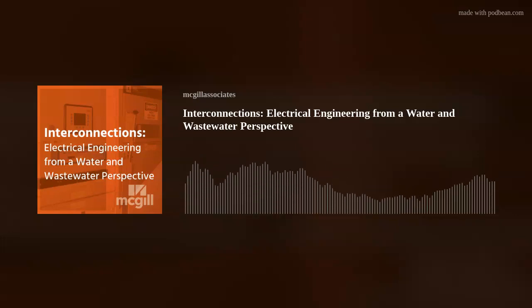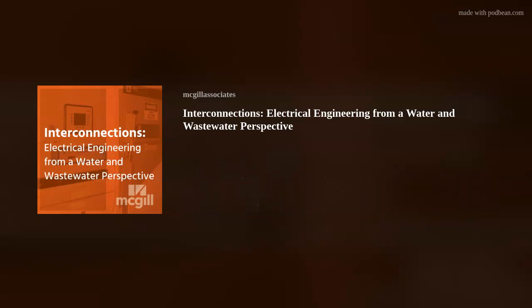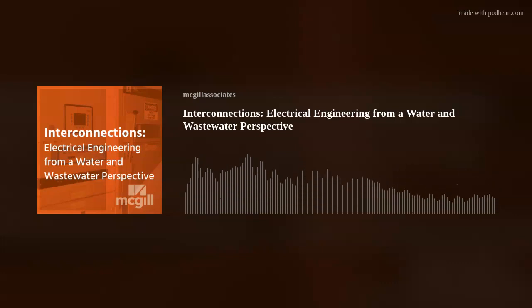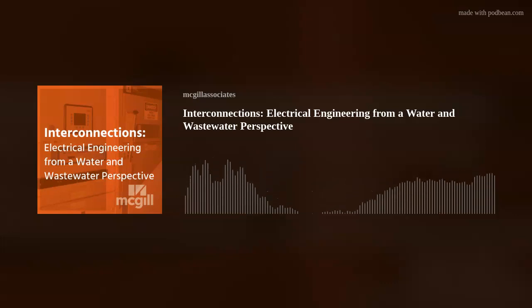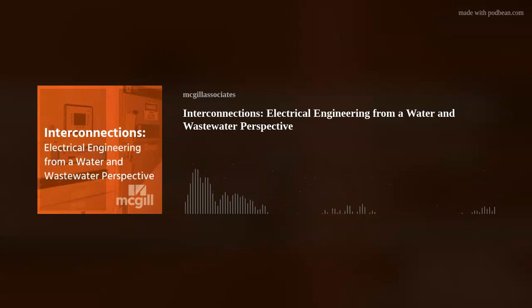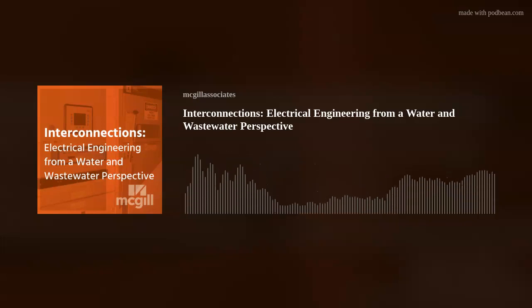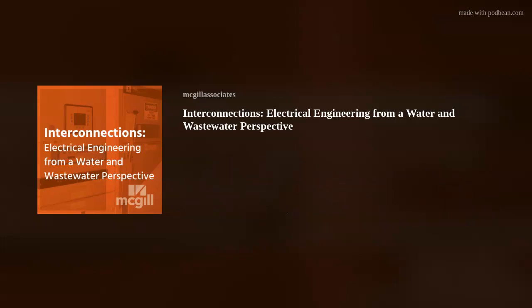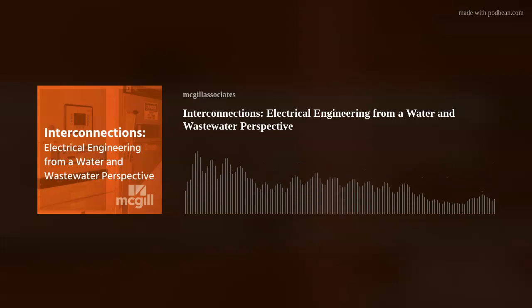This system can have problems which cause the station to go offline. There are backups in place to try to prevent this, but it can happen. Without a SCADA system, with only a local RTU at the site reporting back to a main terminal unit, someone has to be dedicated every day to go ensure the station is operating correctly per NCDENR. With a remote SCADA RTU, that requirement goes down to once a week. That saves man hours, freeing up resources to use elsewhere in the system instead of driving around four hours a day for one person every day. That adds up, reducing mileage and wear and tear on vehicles.